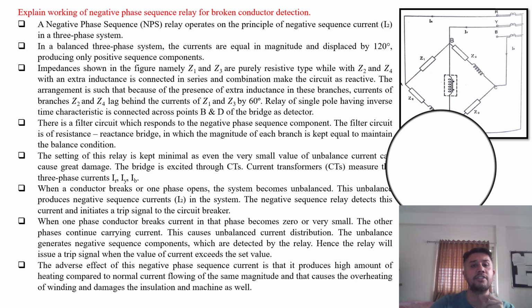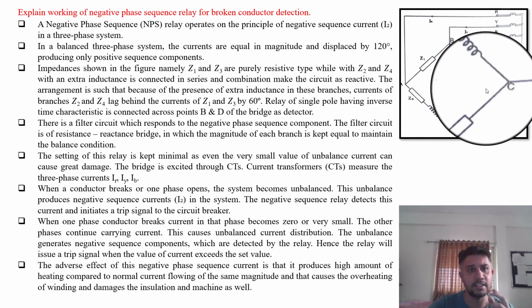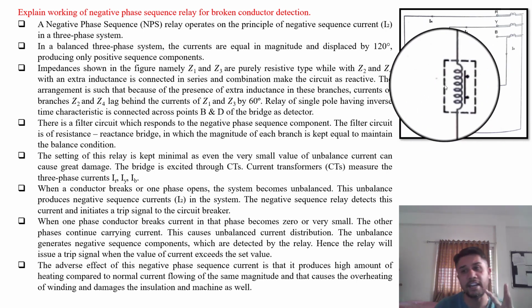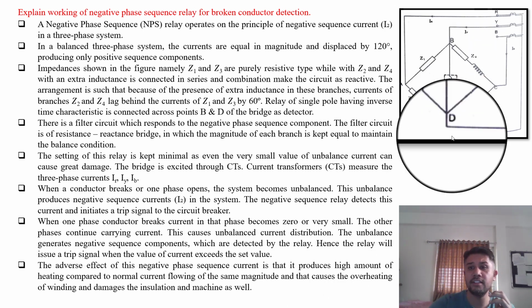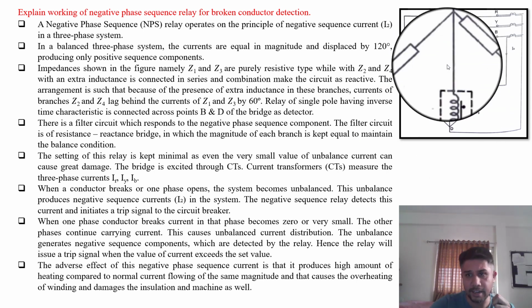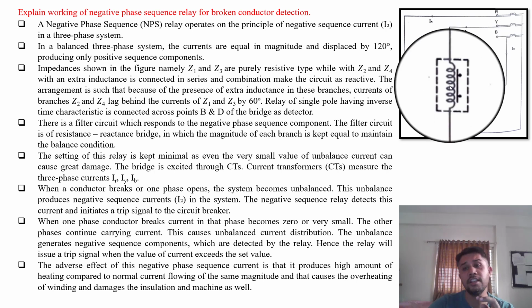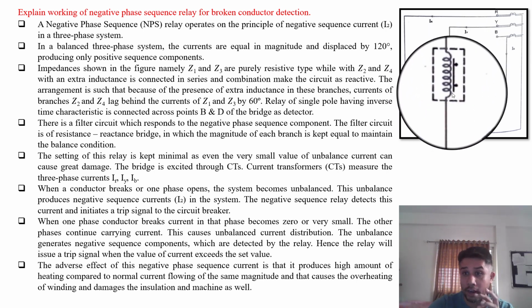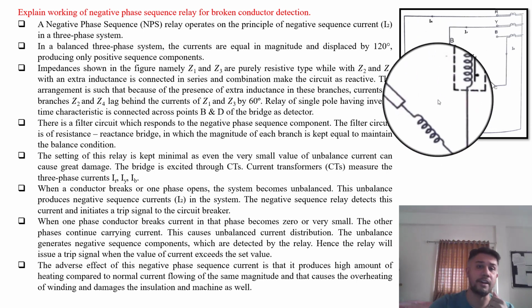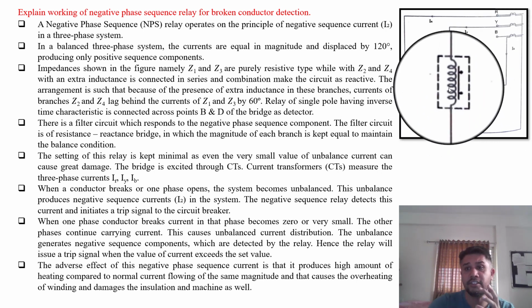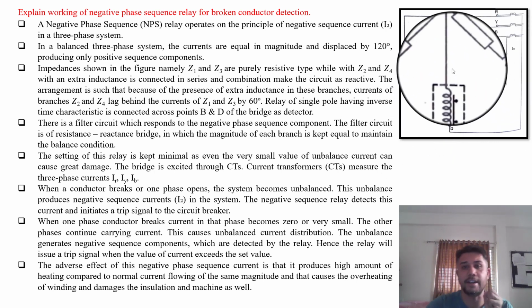The arrangement is such that, because of the extra inductance in these branches, the currents of branches Z2 and Z4 lag behind the currents of Z1 and Z3 by 60 degrees. A single-pole relay having an inverse characteristic is connected across B and D. This is the relay's energizing coil with which the relay operates, and the bridge is connected with the AC supply. It works as the detector.